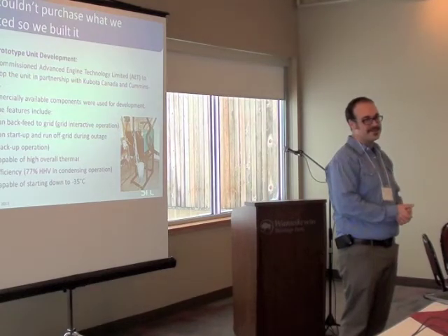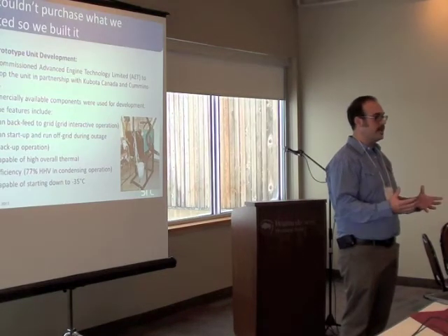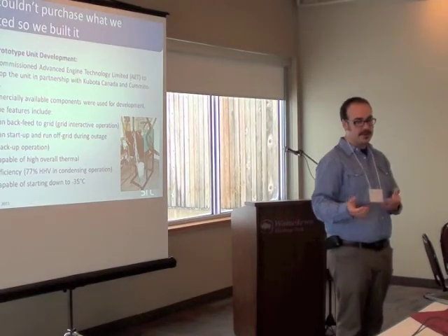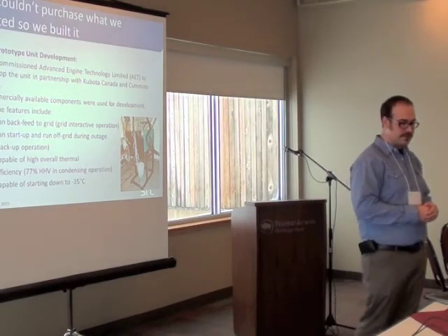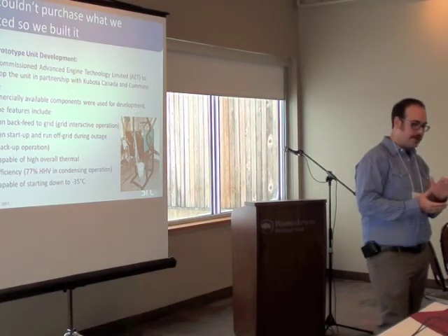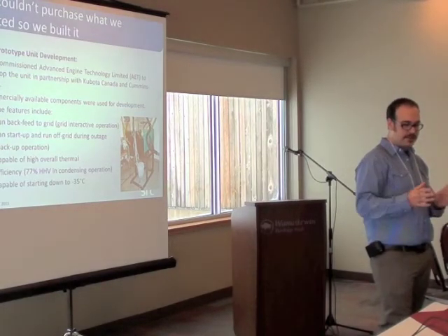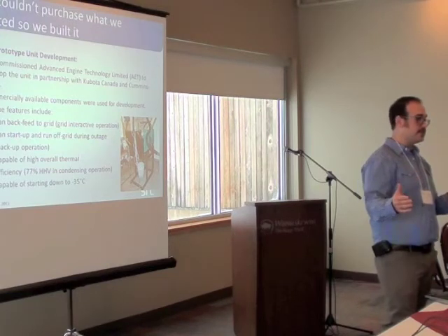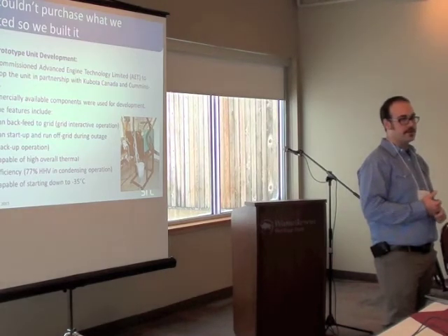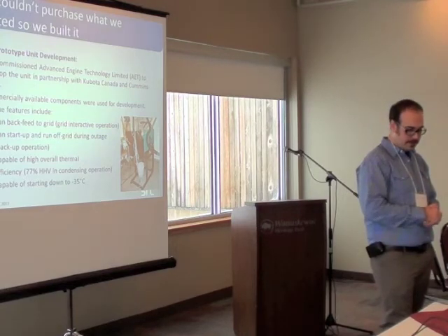We commissioned Advanced Engine Technologies out of Ottawa. They have a lot of experience in building engines and converting engines over to natural gas, as well as adapting heat exchangers. They developed some other combined heat and power systems in the past, and we really felt like they had a good value proposition for us. They used as many commercially available components as possible when they developed this unit. It's actually a Cummins-Onan diesel generator they converted to run on natural gas, added in heat exchangers, built in some components for longer service life, and added in some extra electrical generation systems.